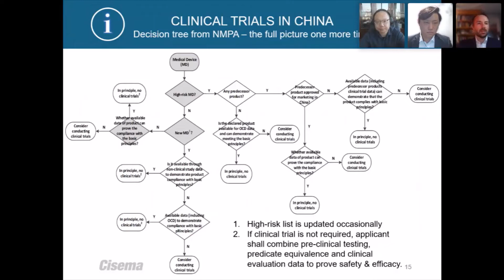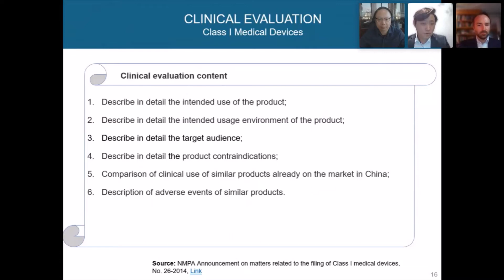Yep. So clinical evaluation reports are required for all medical devices in Europe. In contrast, clinical evaluation reports are not required for Class 1 medical devices in China. However, Class 1 medical devices will still need to show basic clinical evaluation, the content of which is set out in this slide: describe in detail the intended use of the product, the intended usage environment, the target audience, the product contraindications, a comparison of the clinical use of similar products already on the market in China, and a description of the adverse events of similar products.